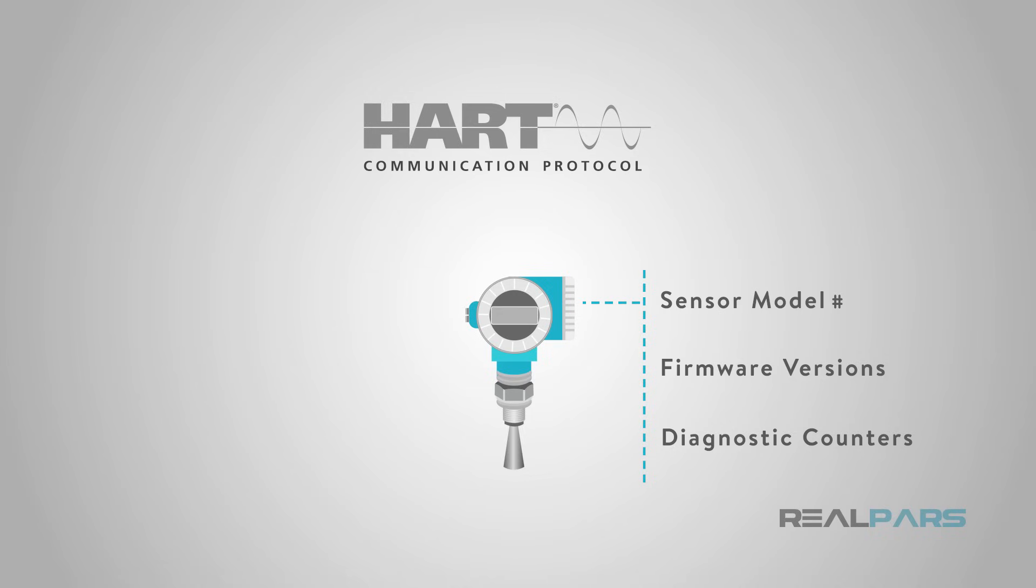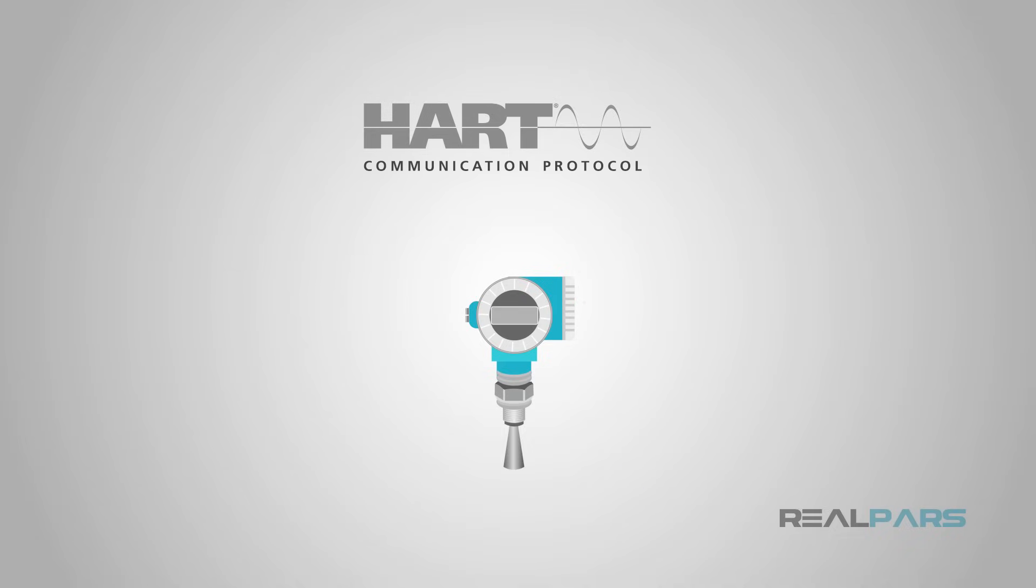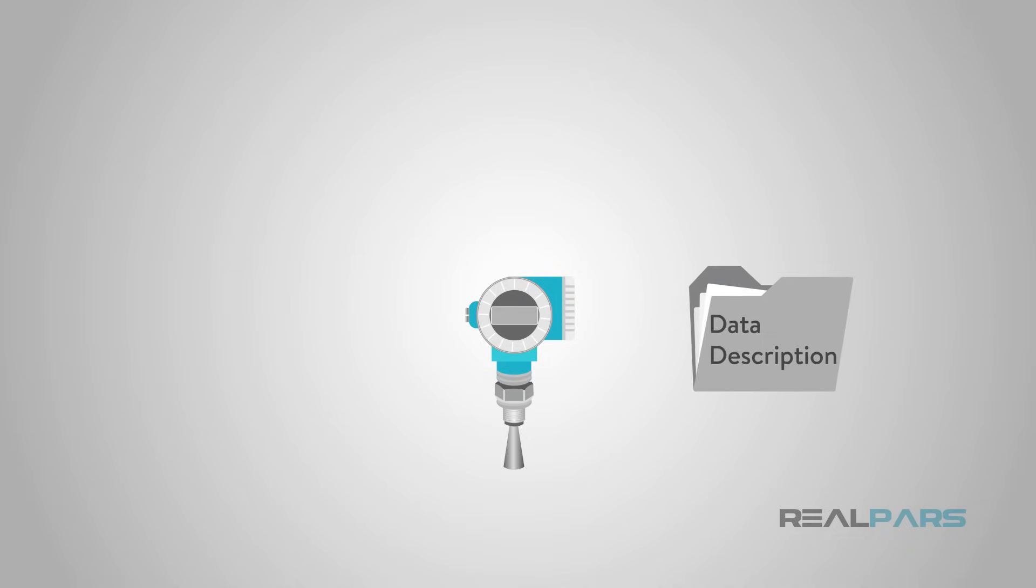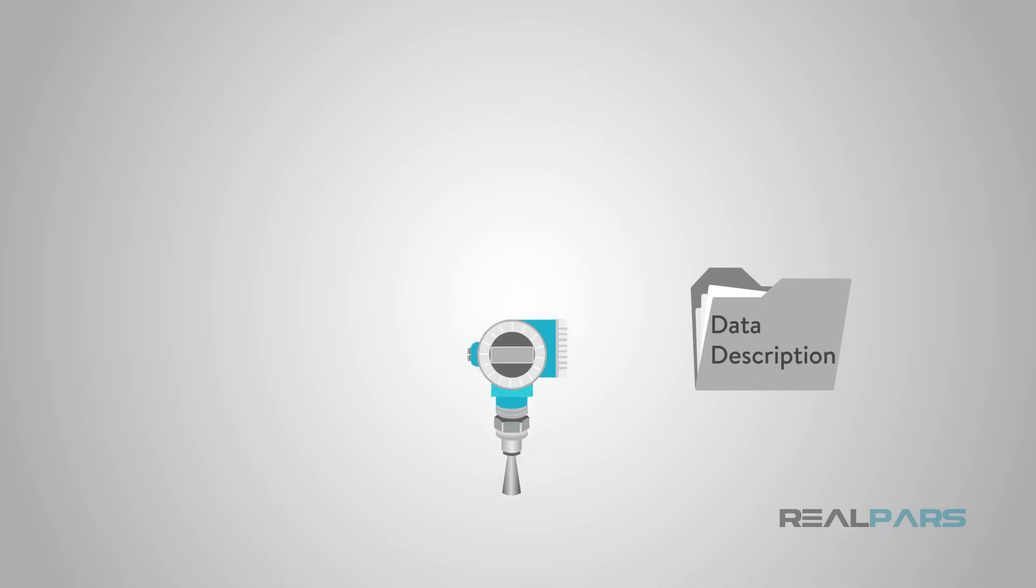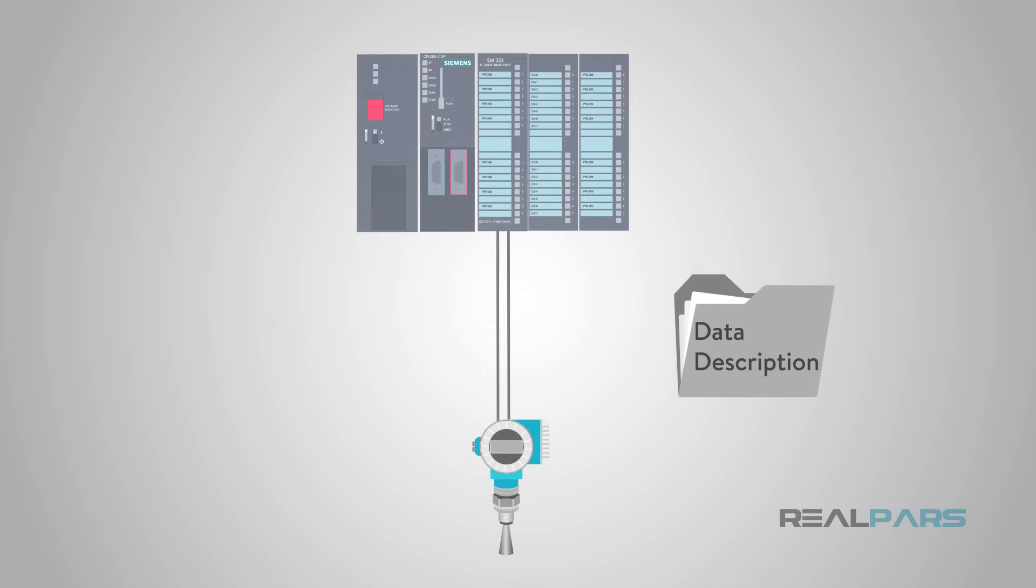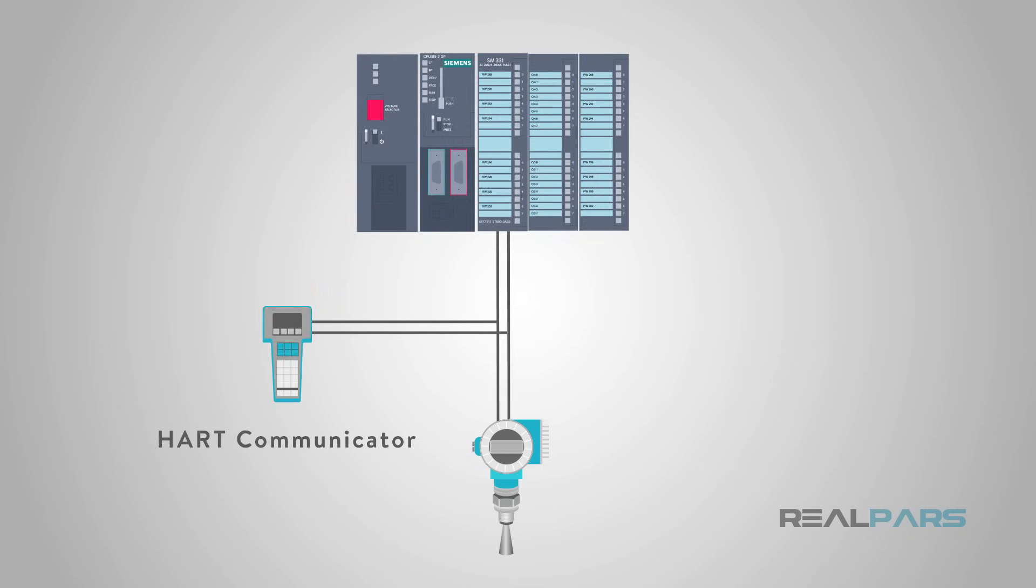In order for the control system to recognize the type and values for these custom data, a special description file called a data description or DD file is required. This file is loaded on the DCS or PLC configuration station or downloaded to the handheld communicator and becomes directly associated to the sensor.